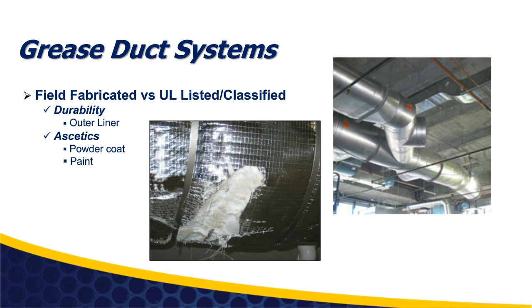So it's really easy, if they're in there doing other trades while this ductwork is in the facility, when they're in there cleaning the systems, it's a lot of risk of damage to that insulation out there. A double wall product has much less risk of damage on site or damage as the system is being hopefully inspected and cleaned on a regular basis. Also, from an aesthetic standpoint, if I've got exposed ductwork in the facility, obviously the outer shell is a lot more aesthetically pleasing. It could be powder coated or painted as well if I've got exposed areas of building versus an insulation with just a foil outer shell on it.